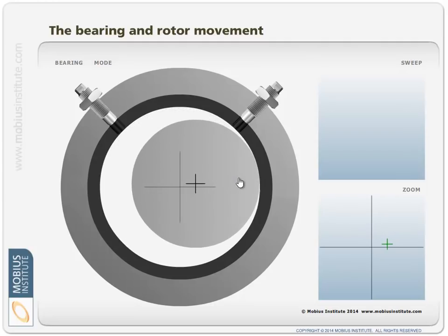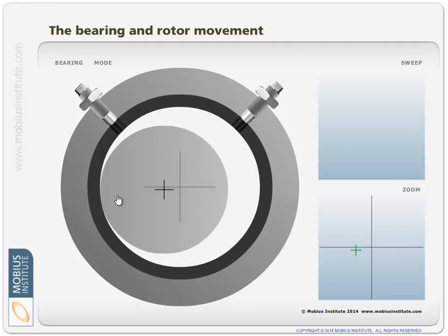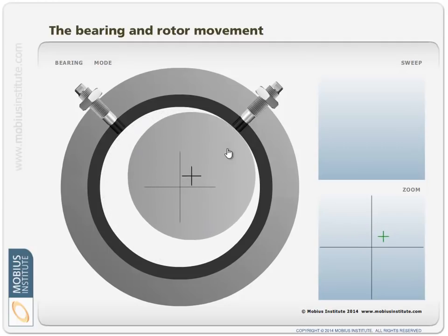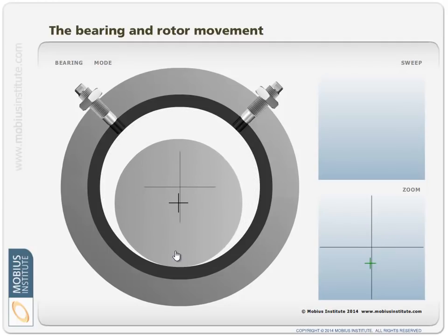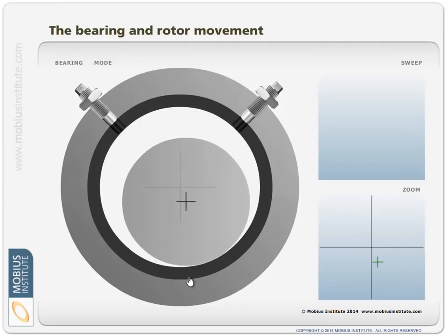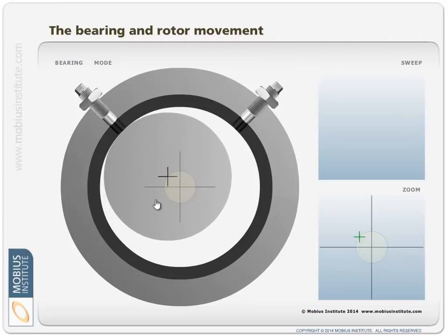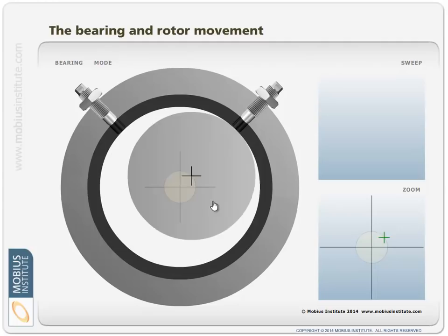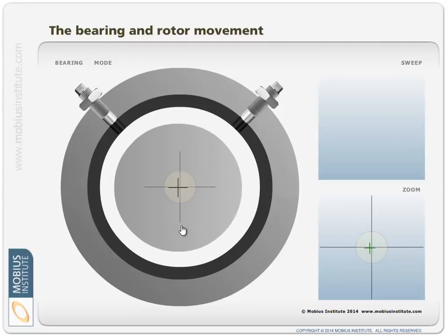That, when it's tracing out that circle there, is the available clearance in the bearing. I don't ever expect to take these gap readings and see that the triangulated position of the center of the shaft is anywhere outside that circle I'm drawing. So rather than using your imagination, there is the circle. That yellowish circle there is the available clearance in the bearing.